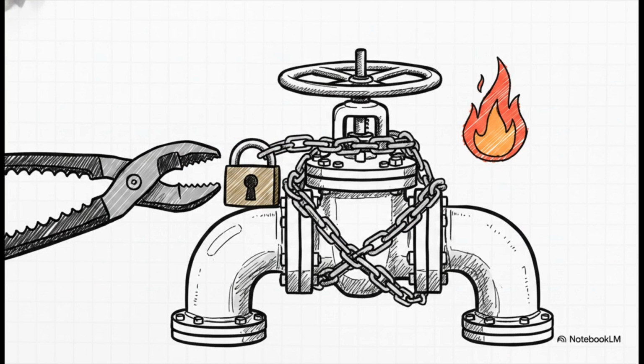And that brings us to the absolute golden rule of overhaul operations. You might be thinking, well, why not just run down to the basement and shut off that big OS&Y or PIV control valve we talked about earlier? The rule is, do not touch the main valve until the fire is out. It is absolutely imperative to ensure the fire is 100% extinguished before cutting off the building's water supply. If you shut that valve even a minute too early, a hidden, smoldering fire can violently reignite, and you'll have absolutely zero sprinkler protection left to fight it.